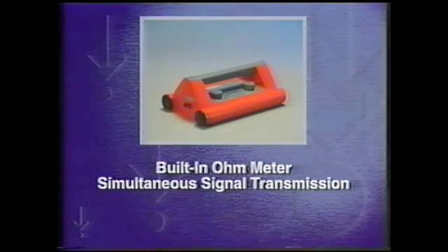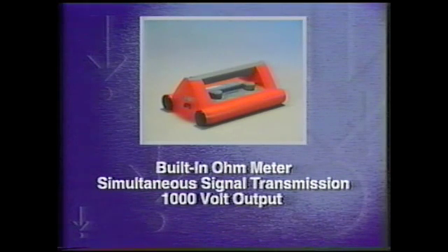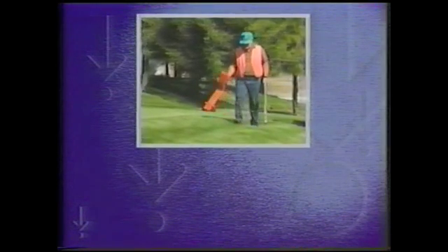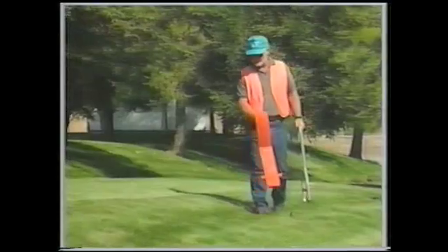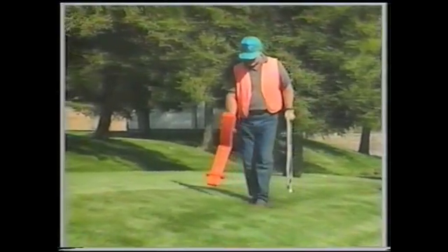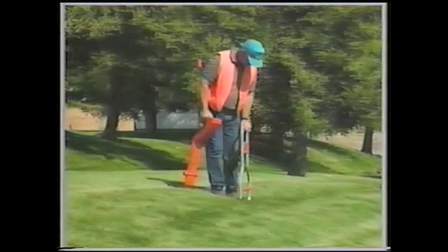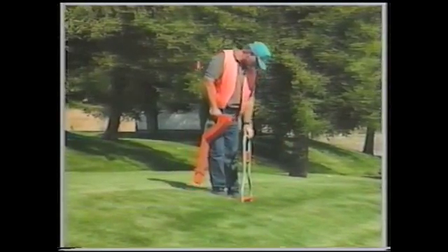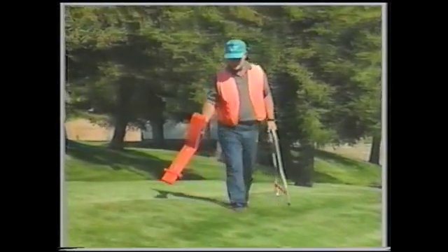The 9800 transmitter with its built-in line resistance meter provides the simultaneous transmission of both fault finding and cable locating frequencies, and a thousand volt output for high impedance faults. Mastering the art of cable fault finding requires skill, experience, and knowledge. By using the Metrotech sheath fault locating system and following step-by-step procedures, you will be able to perform your job faster, safer, and more effectively.